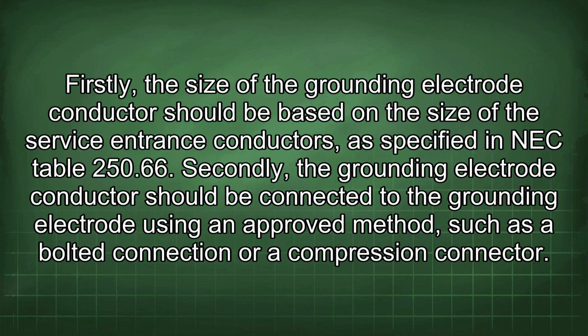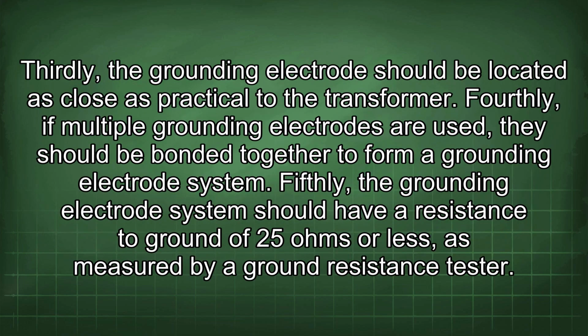Firstly, the size of the grounding electrode conductor should be based on the size of the service entrance conductors, as specified in NEC Table 250.66. Secondly, the grounding electrode conductor should be connected to the grounding electrode using an approved method, such as a bolted connection or a compression connector. Thirdly, the grounding electrode should be located as close as practical to the transformer. Fourthly, if multiple grounding electrodes are used, they should be bonded together to form a grounding electrode system.